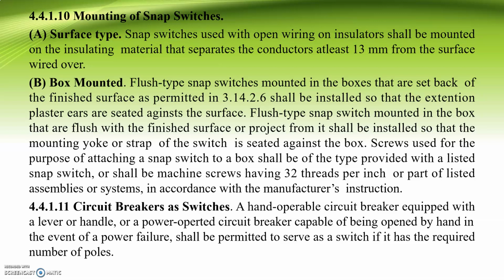So B, box mounted. So flush type snap switches mounted in boxes that are set back of the finished surface as permitted in chapter 3.14.2.6 shall be installed so that the extension plaster ears are seated against the surface. So flush type snap switches mounted in boxes that are flush with the finished surface or project from it shall be installed so that the mounting yoke or strap of the switch is seated against the box. So screws used for the purpose of attaching a snap switch to a box shall be of the type provided with a listed snap switch, or shall be machine screws having 32 threads per inch, or part of listed assemblies or systems in accordance with the manufacturer's instructions.